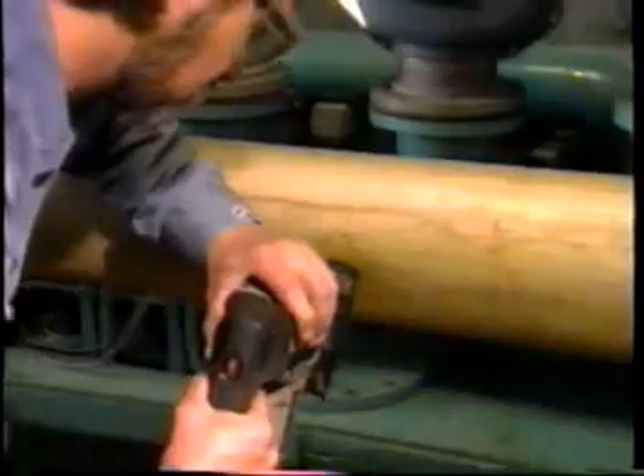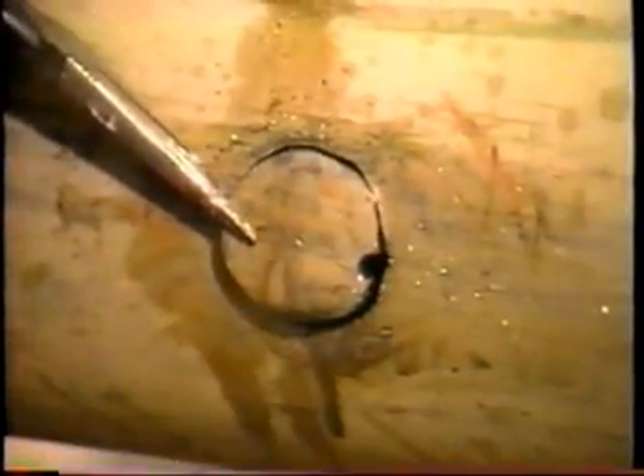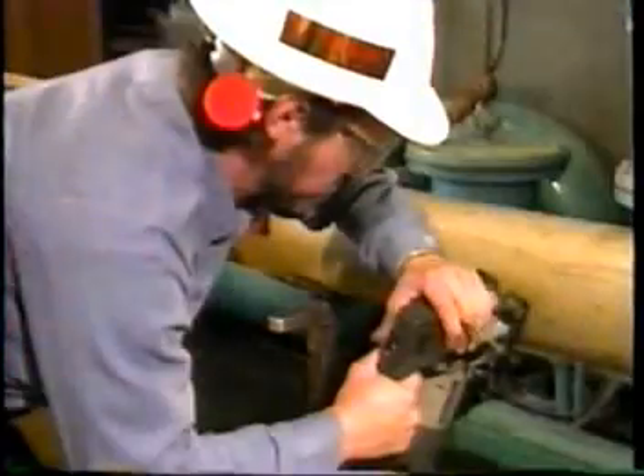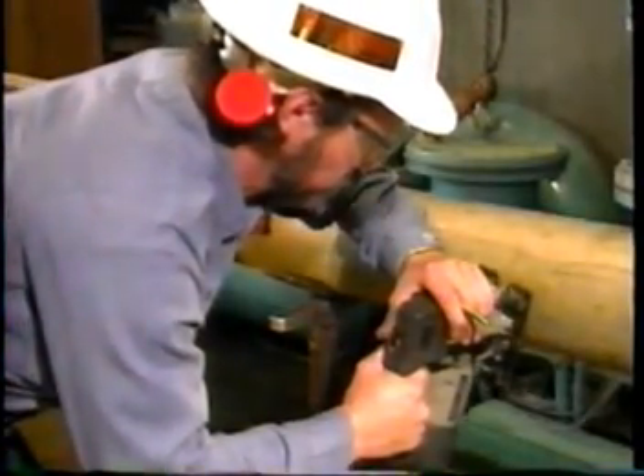Once the site has been selected, the probe can be installed in a matter of a couple of hours. Once the hole for the probe has been cut, it is essential to also allow room for inserting breaker bars just upstream and downstream of the probe location.